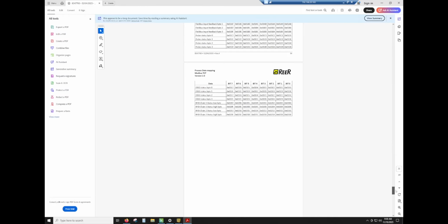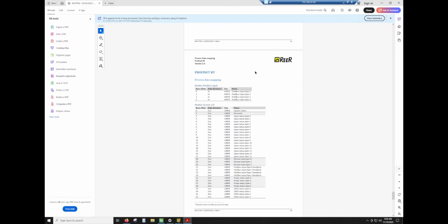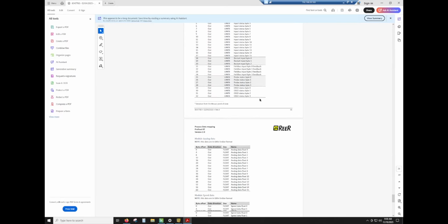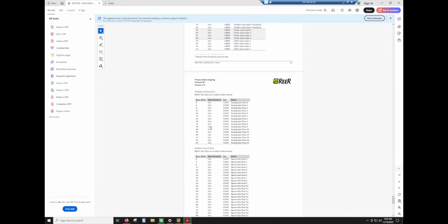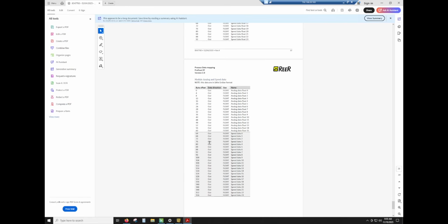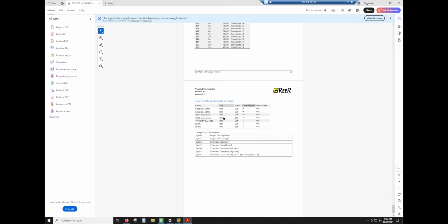So now in page 36, you can see that all of this is mapped out for us here. Our OSSD statuses, our analog data, our speed data if we need it. And then if we get to the end, we get to this record data. Now, because we're using the RFIDs in our project, we want to know which RFID sensor was tripped. So if we have 5 in line, we could name each door 1 through 5, and then if somebody opens door 4, we could actually read from the safety controller that door 4 has been opened.